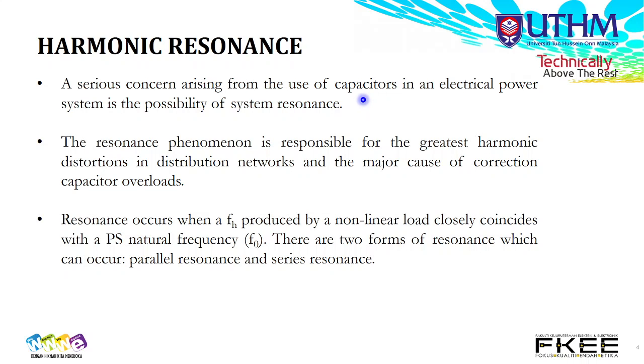The use of capacitor in an electrical power system introduces the possibility of system resonance. The resonance phenomena is responsible for the greatest harmonic distortion, producing high harmonic distortion in the distribution networks, and is the major cause of correction capacitor overload.